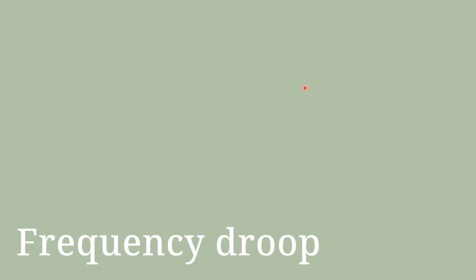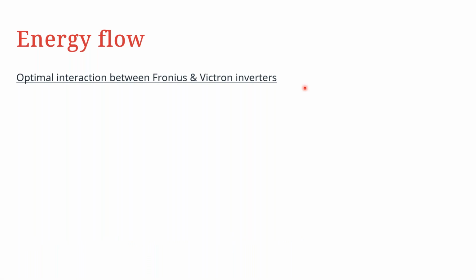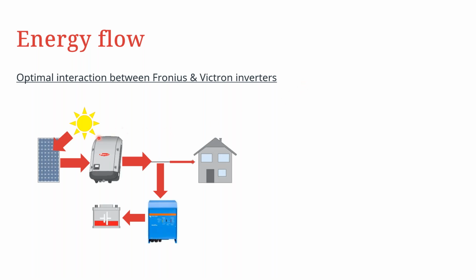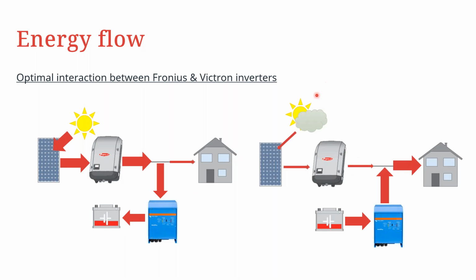So let's now look at the frequency droop. There needs to be optimal interaction between the Fronius inverter and the battery inverter, in this case the Victron inverter charger. We look at a situation whereby the PV array is generating a sufficient amount of power, and all this power is converted by the Fronius inverter. Some of it goes to the loads, and a lot of it goes through the Victron inverter for recharging the batteries. In the case that you do not have sufficient production by the PV array, so there is minimal production, then the batteries through the Victron inverter should be able to cover the gap that is not being delivered by the PV side.